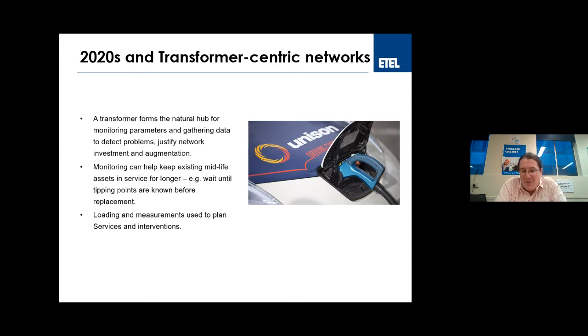So all this is - suppose if we have a transformer somewhere and more loads get put onto it, the utility might not really know how it's being loaded, and they might be concerned with loading it too much. We think monitoring will help save in the long run, because if monitoring is put on a transformer in that situation, and the utility is happy that the load is not getting too high, then they can keep running that transformer.